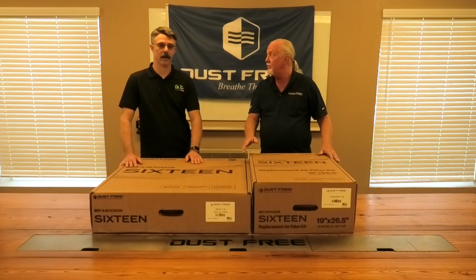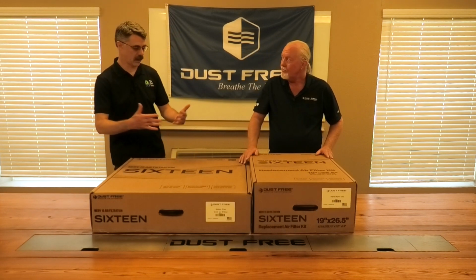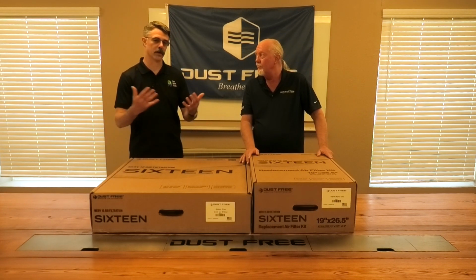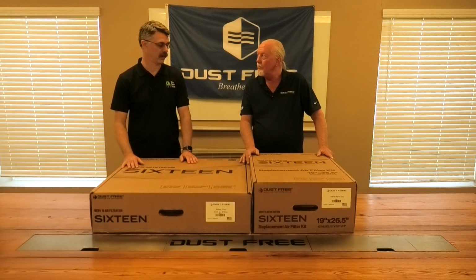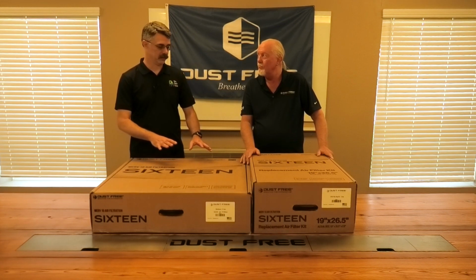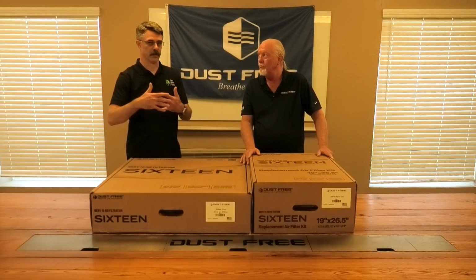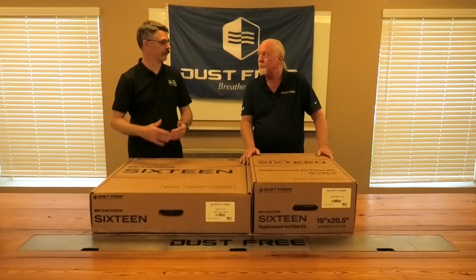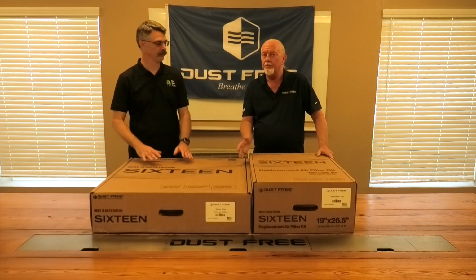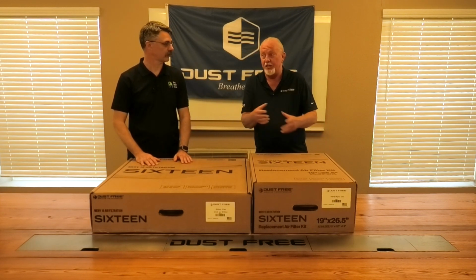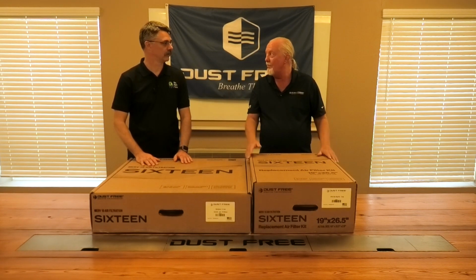Does that make sense? Yeah, absolutely. Because it makes a difference on how you design that whole system, the ductwork and everything else in the rest of that system. And the more static pressure we can have for the rest of those components, the smaller we can make them. And if that filter eats too much of it up... Sure. We have a static pressure budget that we've got to go shopping for our system.